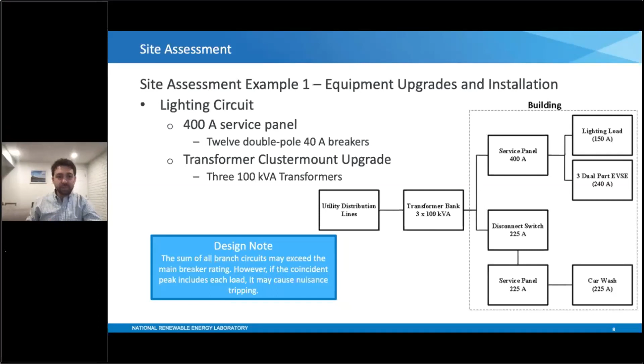And essentially what that just means is just because you have 10 different 20 amp circuits doesn't mean that your main breaker needs to be rated to supply all of those loads, because they most likely won't be on at any given time. However, that is the most conservative approach. And if you are a little bit less conservative and you have a smaller main breaker rating, then what's going to happen is this nuisance tripping, where if too many lights or too many devices are turned on, your main breaker will trip open and turn off the devices. That's another great question to talk with your electrician to have a pros and cons on what is the best sizing for all of these circuits.